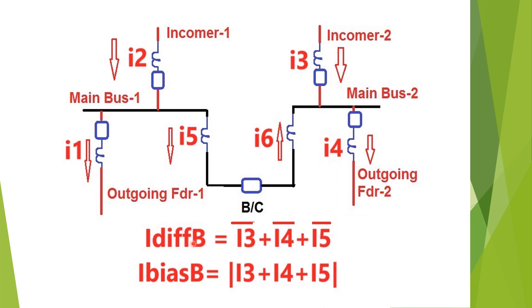Similarly, for zone B, i_diff_B is the vector sum of i3 (incomer two), i4 (outgoing feeder two), and i5 (CT on the main bus one side). The bias current for zone B is the scalar sum i3 + i4 + i5.